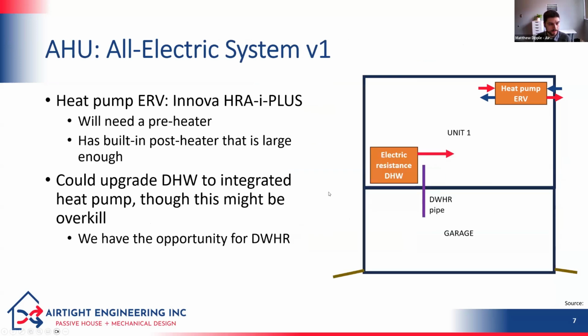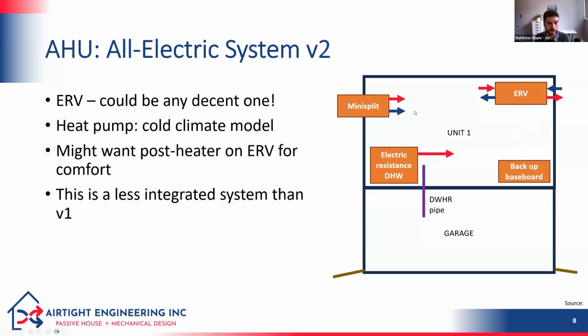For the additional dwelling unit, I think the heat pump ERV combo units are nice and fit well with that type of unit. I like them because you can still duct to all the rooms if you have a few different rooms, and it's nice and integrated - you don't need a separate baseboard heater that's less integrated. That's my preferred proposal, but a second option would be a traditional mini split with a regular ERV and backup baseboard resistance heat.